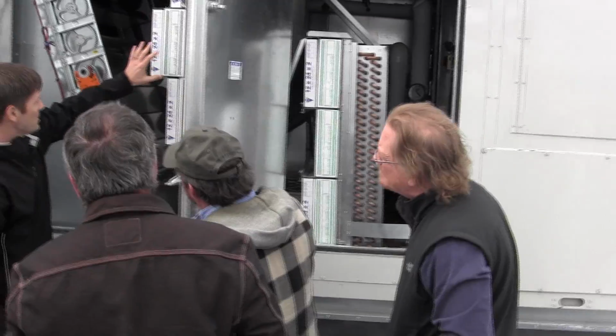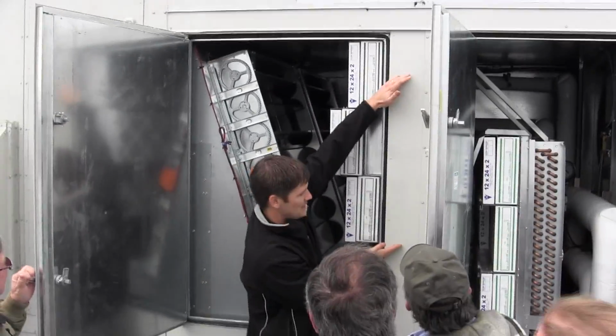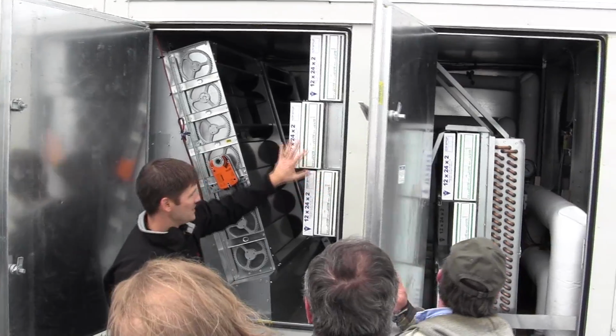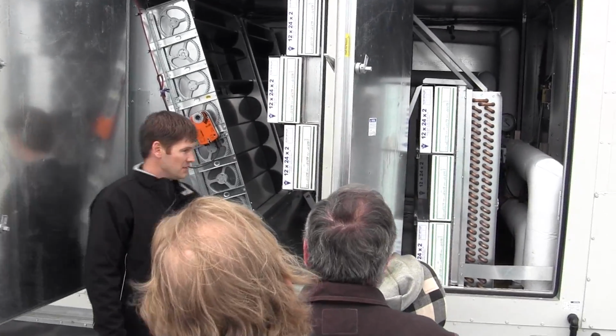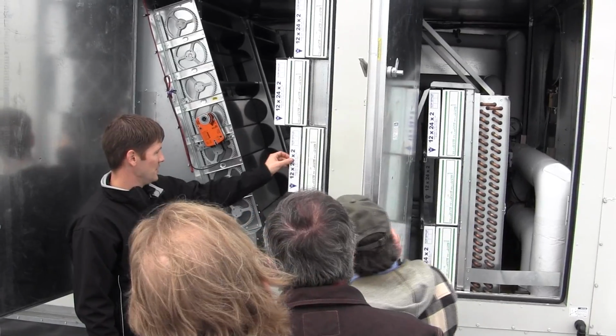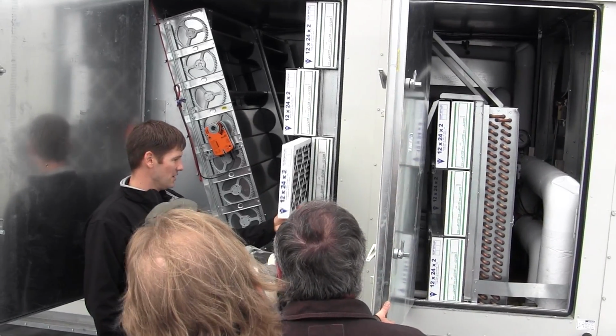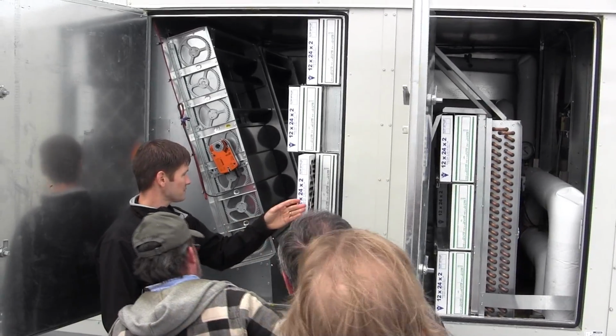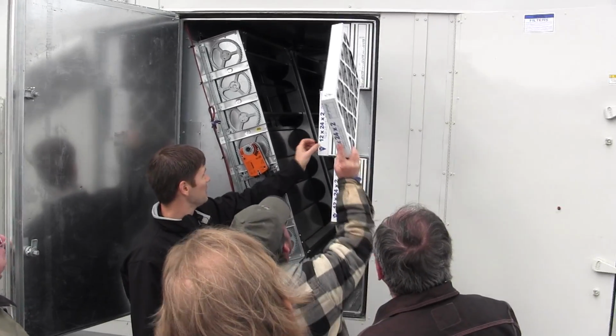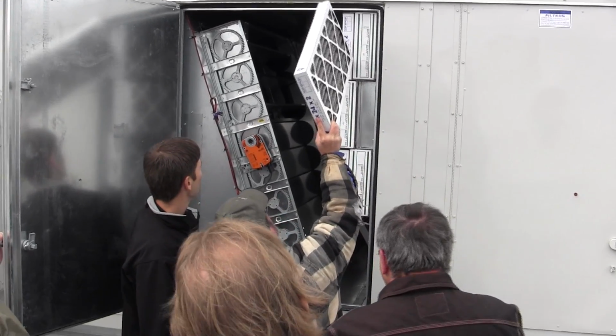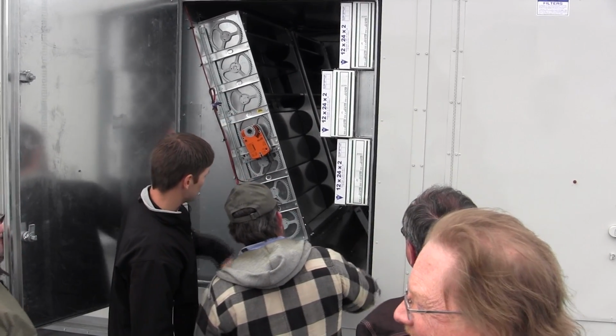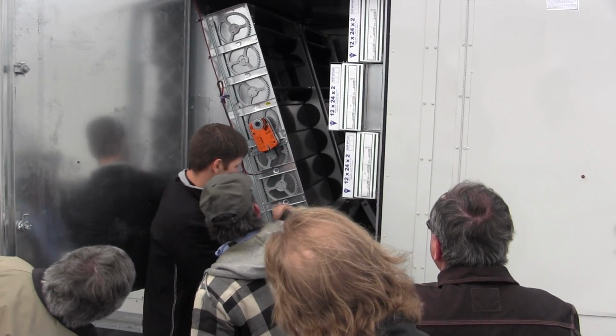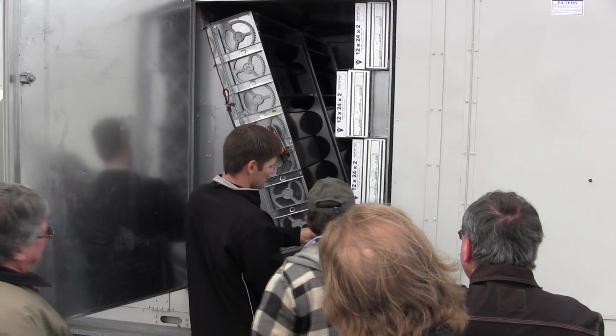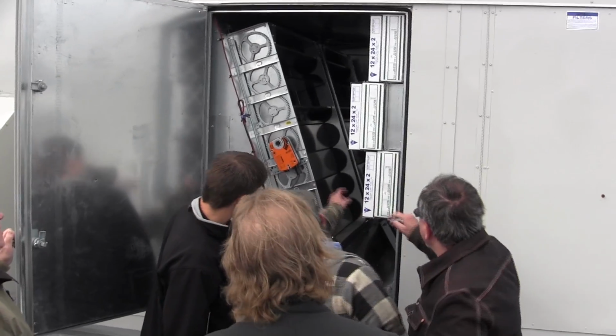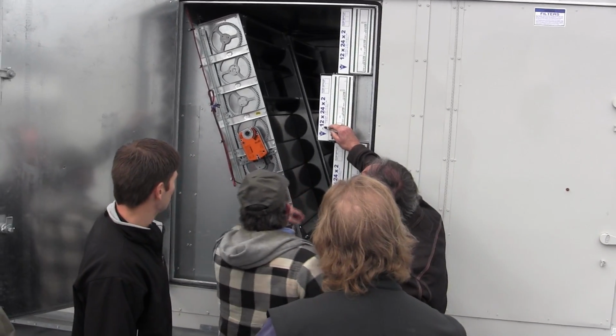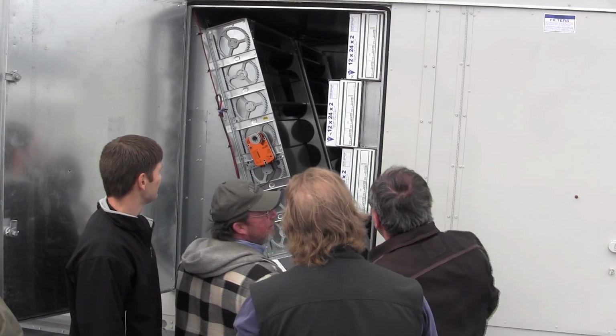Okay. So there's a DX coil right here, and there's a DX coil over there. These filters are for one coil, those filters are for the other. They're essentially the same filter rack, so these would be redundant as well. And as you can see, they are pretty darn clean. So just that first one there, this first one, I recommend taking that out. Wow, it looks like it's missing down there. Oh, it's right there. Where'd you get this one? This one was over there. Those two are in the far corner. I'll go on the other side and get those. I was wondering why they wouldn't slide.